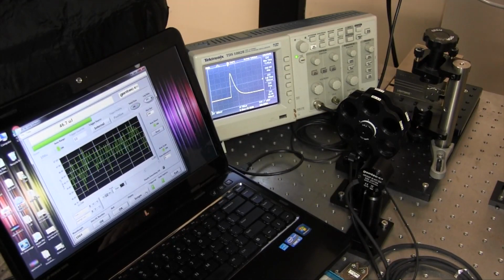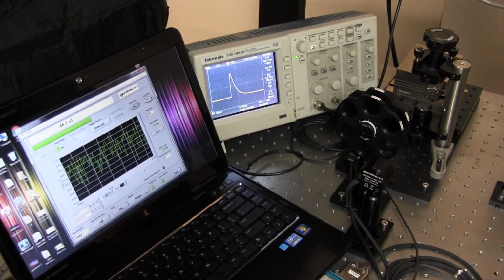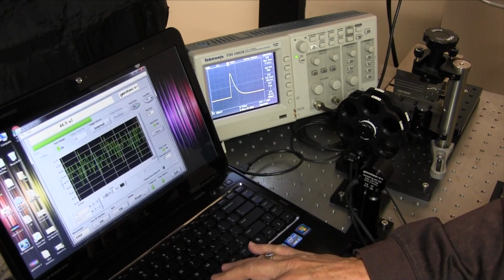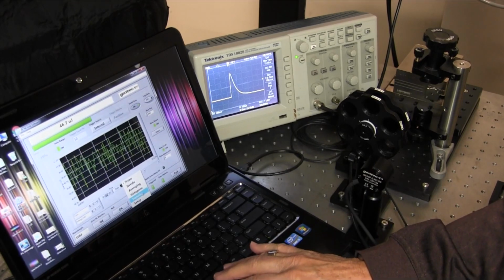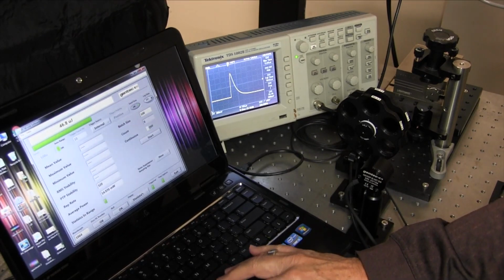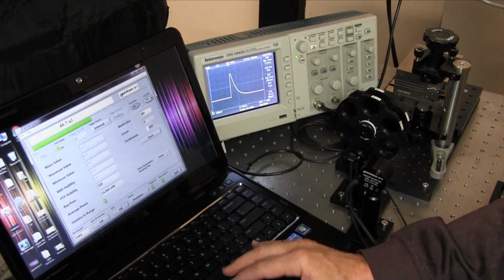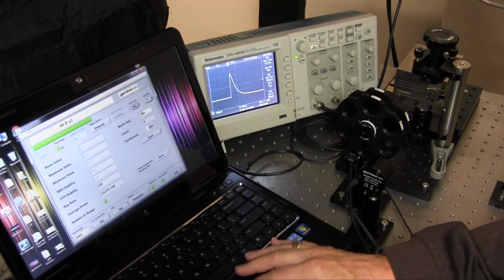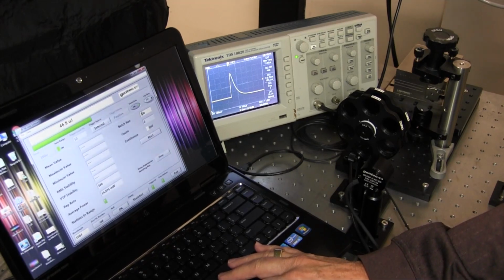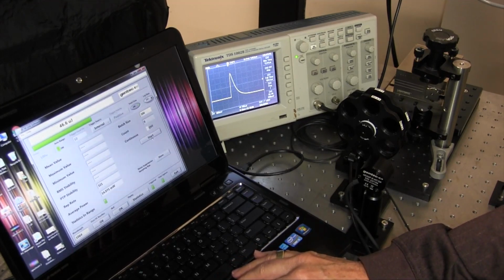Let's set the M-Link up to take a data set in the statistics mode of operation. I'll go down here and select this stats mode. I'm going to set the batch size to 300 pulses, as the laser is running at about 320 pulses per second. I'll hit start.